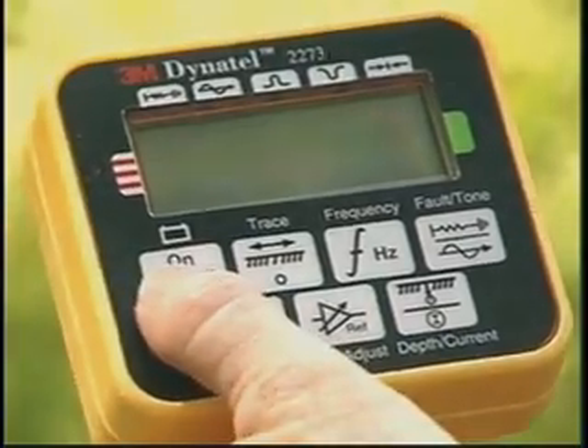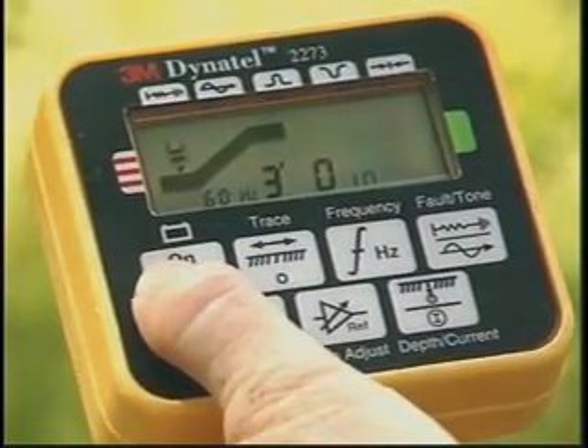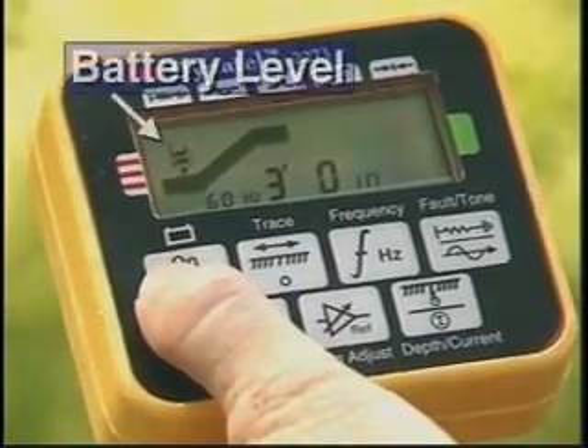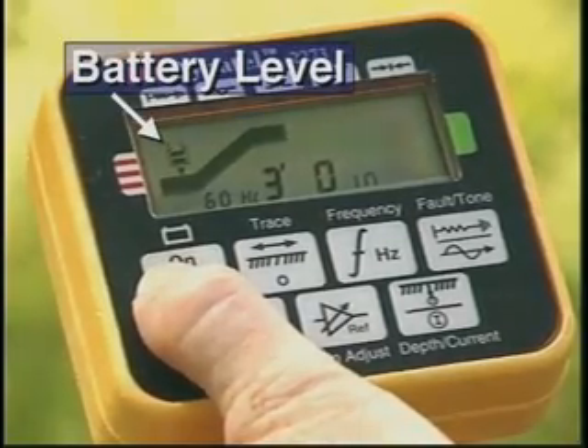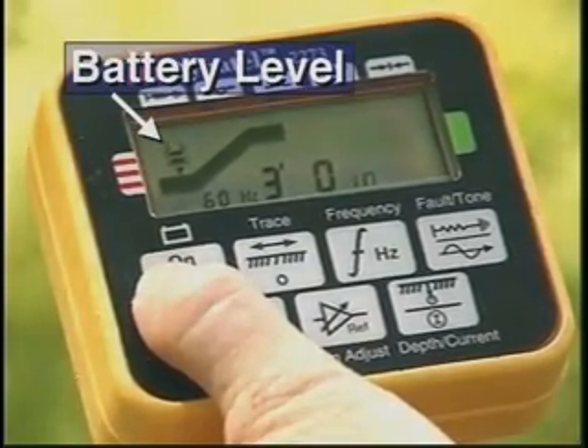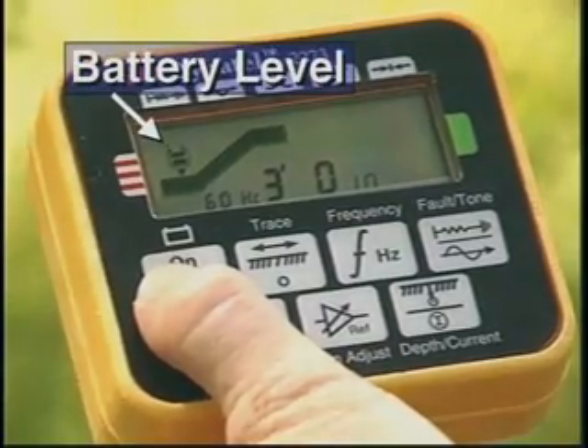Tracing the cable path with the receiver is a simple process. Turn the unit on by pressing and holding the on-off key. Notice the battery level mark on the left side of the bar graph. If the bar graph is to the left of this mark, you'll need to replace the batteries.